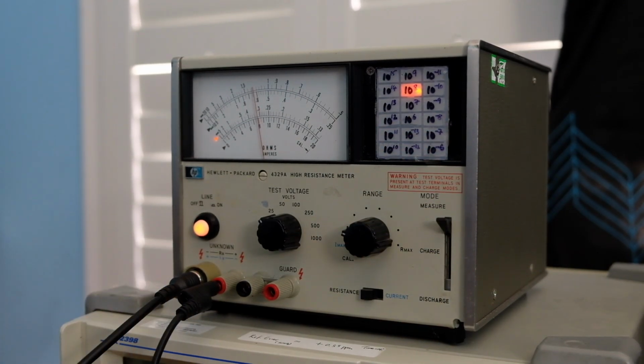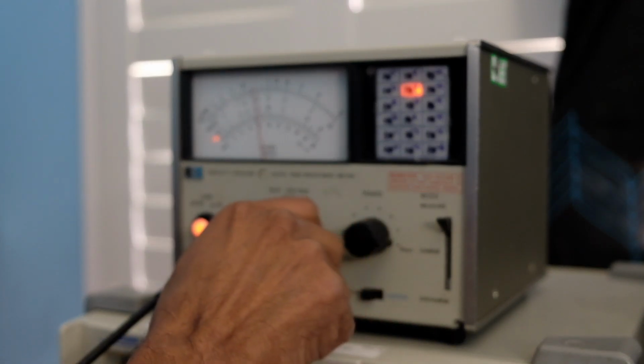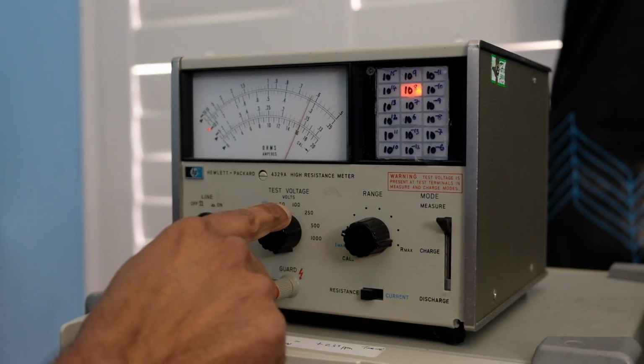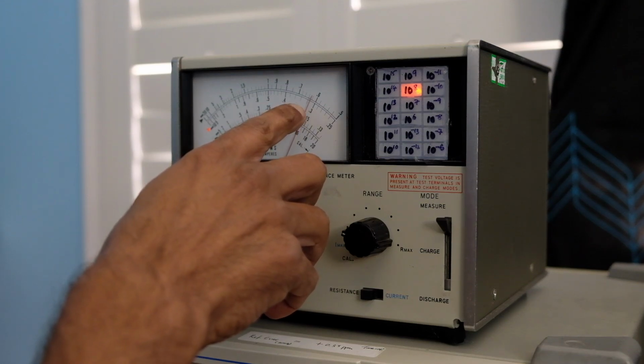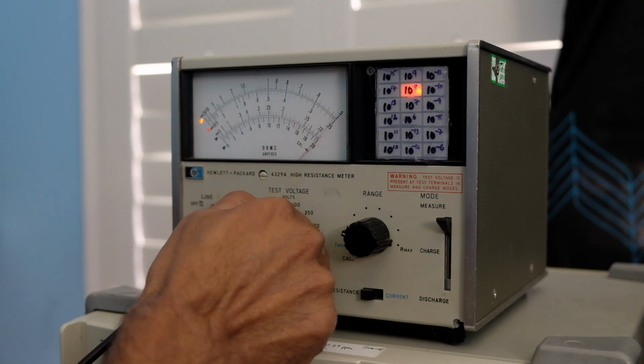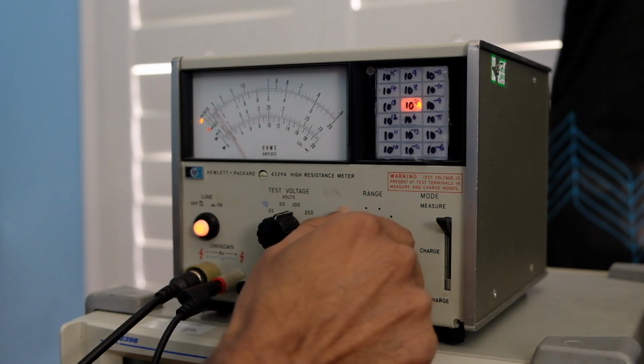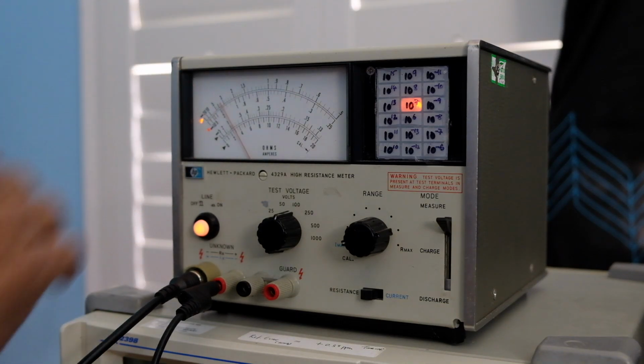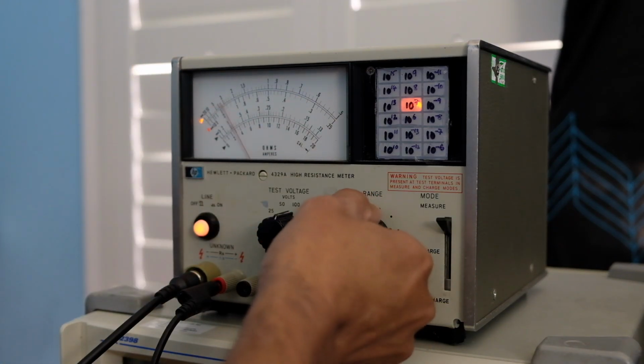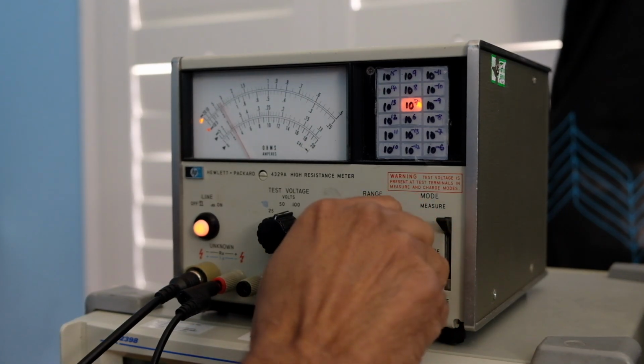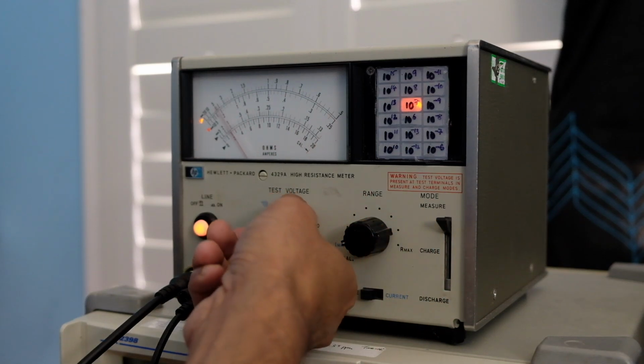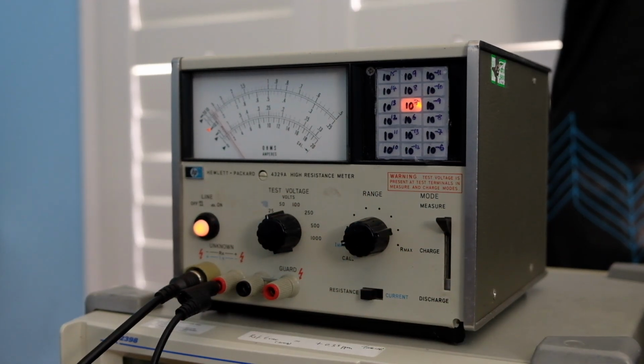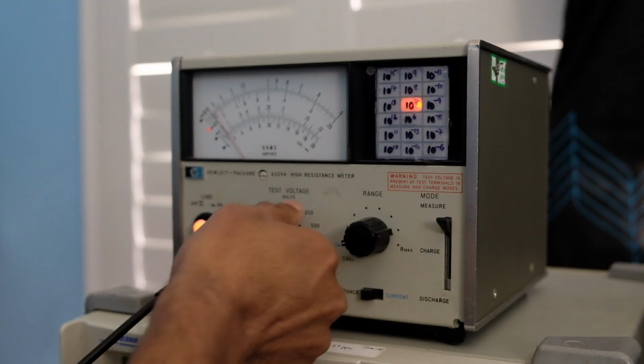As you can see, it's actually reading 31 mega ohms, which is pretty okay, I guess, for this range. Let's see if I can get it at a different voltage. On a 50 volt test, I'm seeing again 31 mega ohms, same value. On the 100, it's also reading around, yeah, it's basically not enough resolution on this scale, but it's a little over 30, 31, 32 mega ohms again. It's pretty useful. If you want to measure into the hundreds of mega ohms and giga ohms and above, I think this meter will have no problem doing it.